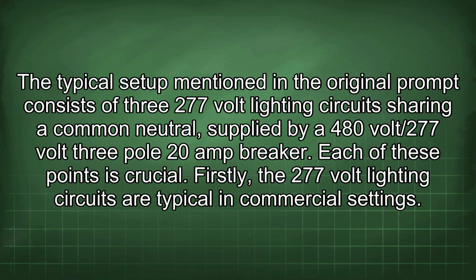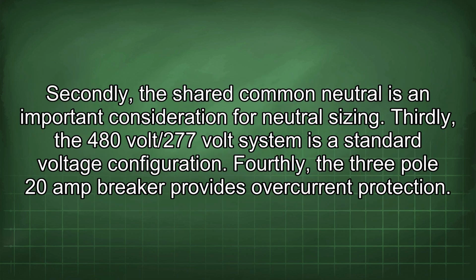The typical setup mentioned in the original prompt consists of three 277-volt lighting circuits sharing a common neutral, supplied by a 480-volt/277-volt three-pole 20-amp breaker. Each of these points is crucial. Firstly, the 277-volt lighting circuits are typical in commercial settings. Secondly, the shared common neutral is an important consideration for neutral sizing. Thirdly, the 480-volt/277-volt system is a standard voltage configuration. Fourthly, the three-pole 20-amp breaker provides overcurrent protection.